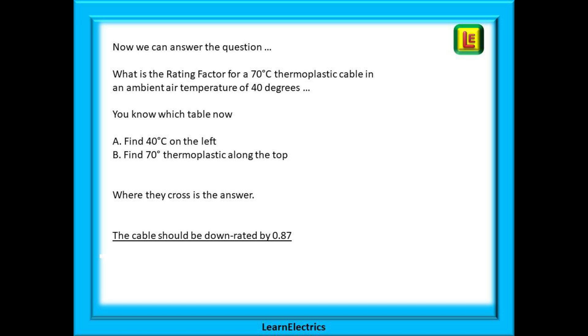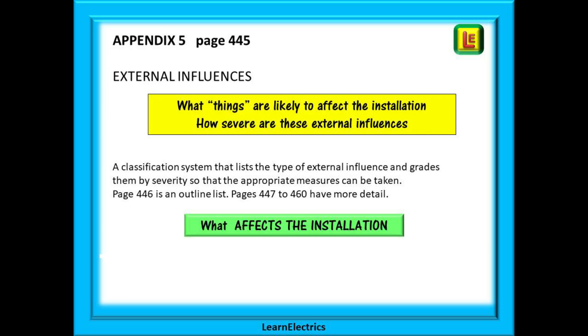This means that at 40 degrees a 10 amp cable should only be expected to carry 8.7 amps before it overheats. Appendix 5 starts with a list of all the external influences that might have an effect on an installation. Become familiar with the layout of page 446 and what is on it. If you need more information, the following pages contain more detail for each influence type.